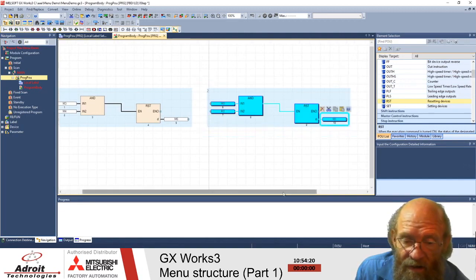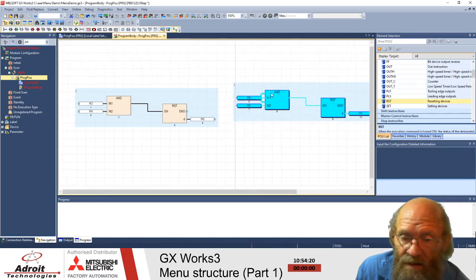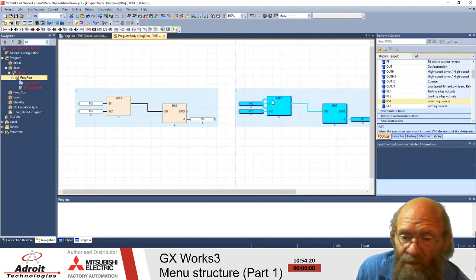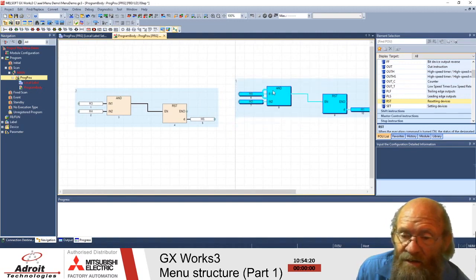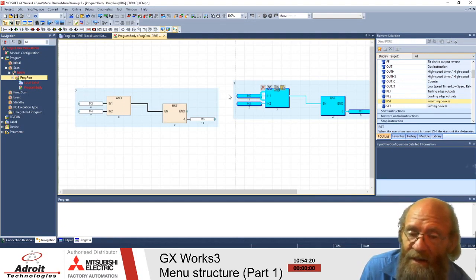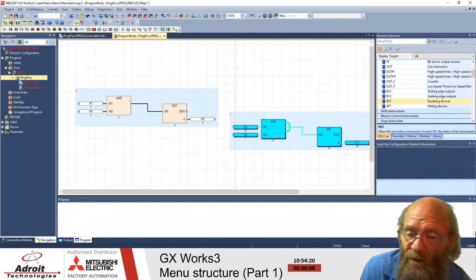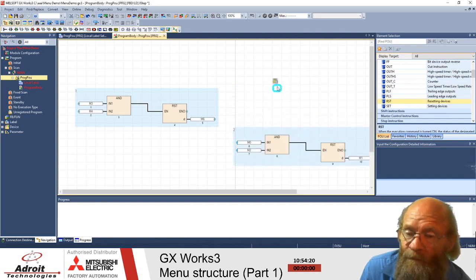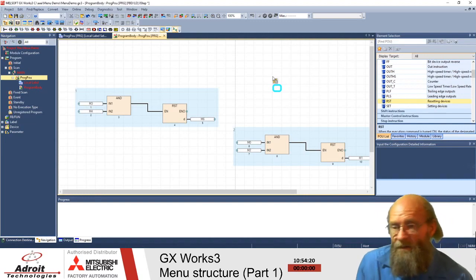Take note what's going to happen now. I select my code and I just move it one line up. Did you see what happened? We change sequence. Okay, have a look here. This part of the program is going to run before that part, although you think because this is that side it's going to happen first. No, it's not. This side will happen first now, until I make it either equal or below. Okay, just a little hint there.